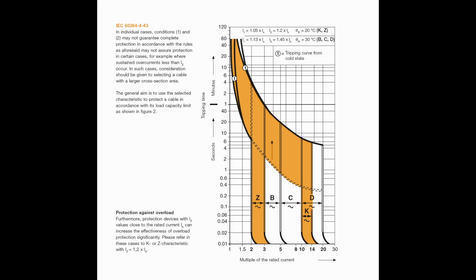And essentially what we've got here, along the bottom of the graph, is the multiple of the rated current. So that's the values we were just talking about. So we've got type B in the middle there. You see it starts between 3 times and 5 times, and then the type C is between 5 and 10, and type D is between 10 and 20. And this particular one also has the type Z and K, so that's the 2 to 3 there at the bottom, below the B, and then K is fitting in as a subset of D between 10 and 14.